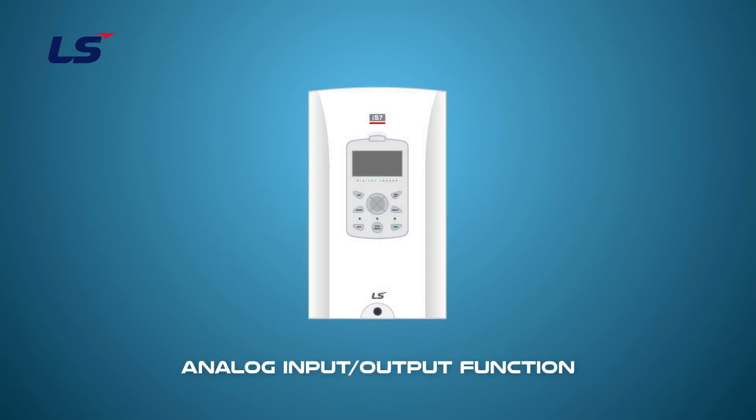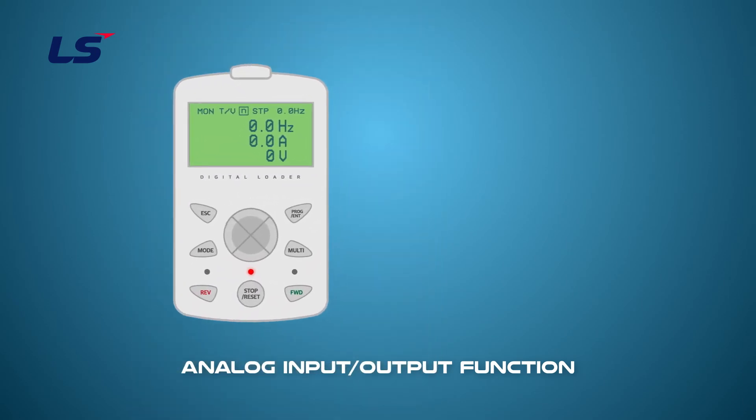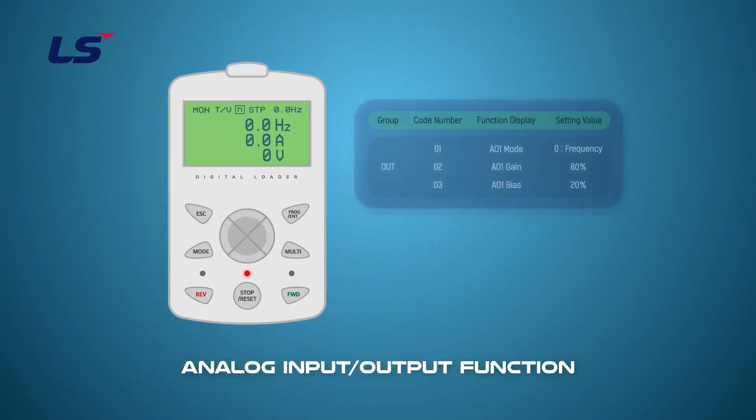Next, we will learn how to use the keypad to monitor the current frequency through the output of 2 to 10 volts. In this video, we will set the output to 2 volts at 0 hertz and 10 volts at 60 hertz.